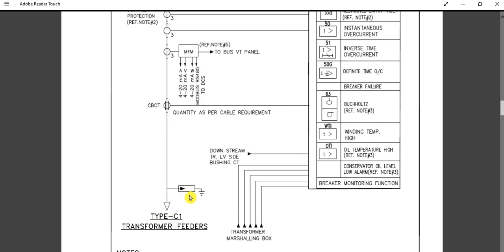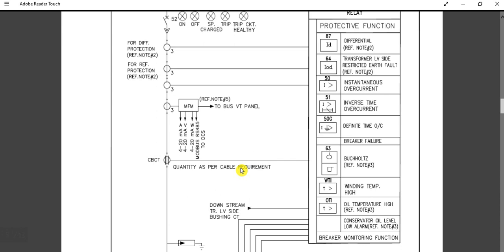There is also a surge arrestor, which is required for the transformer outgoing feeder protection. Regarding MVA rating: for transformers rated 5 MVA and above, the 87 differential protection and 64 earth protection can be provided. For transformers 10 MVA and above, these protections are a mandatory requirement. For transformers below 5 MVA, the 87 and 64 protection functions are not required.